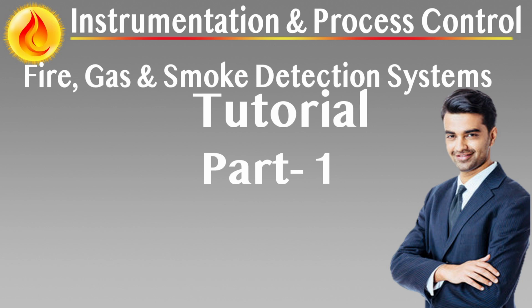In summary, point gas detector technology must align with the environmental and process demands of the installation. Infrared detectors are the primary standard for most hydrocarbon applications, while catalytic detectors are reserved for legacy or constrained use cases. Aspirated detection provides coverage where neither IR nor catalytic sensors can physically survive, but demands careful design and monitoring to ensure reliable operation.